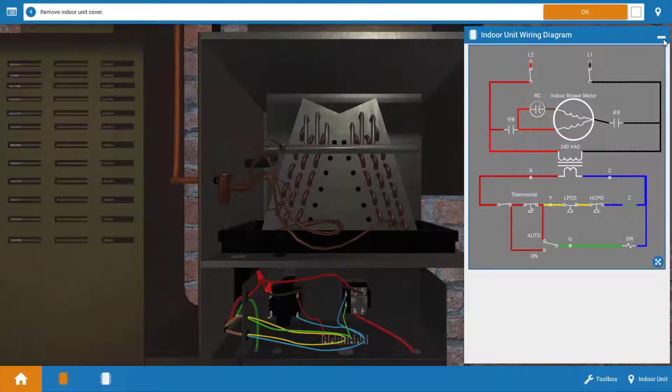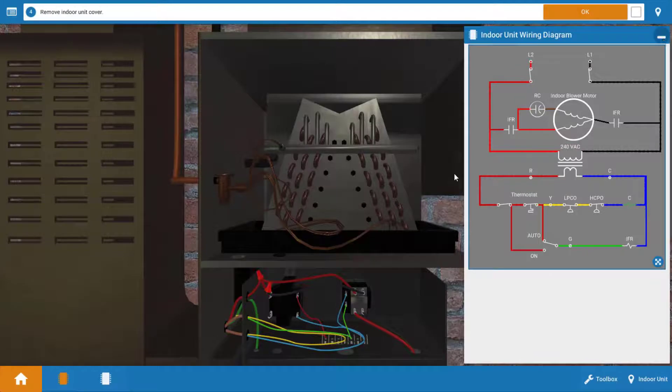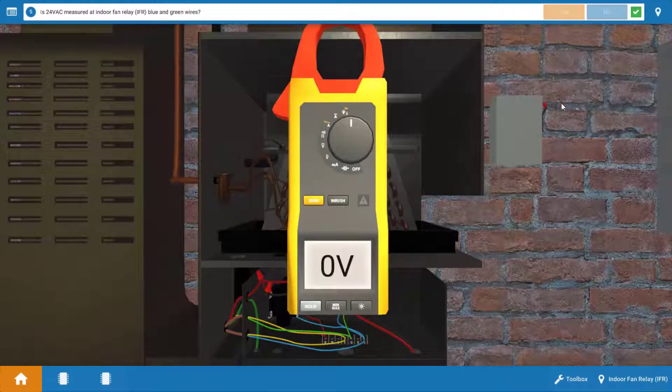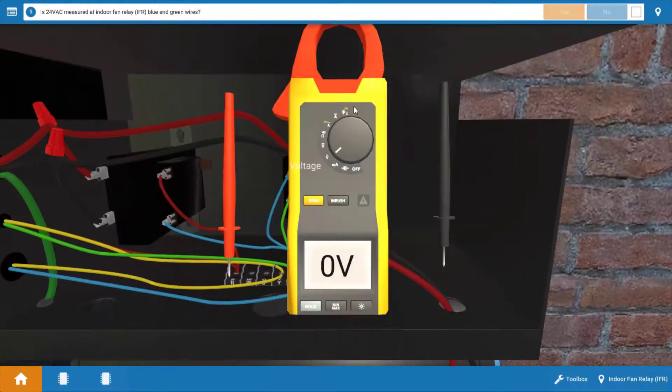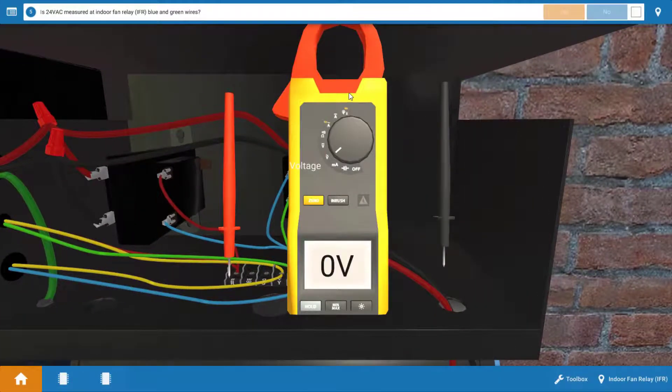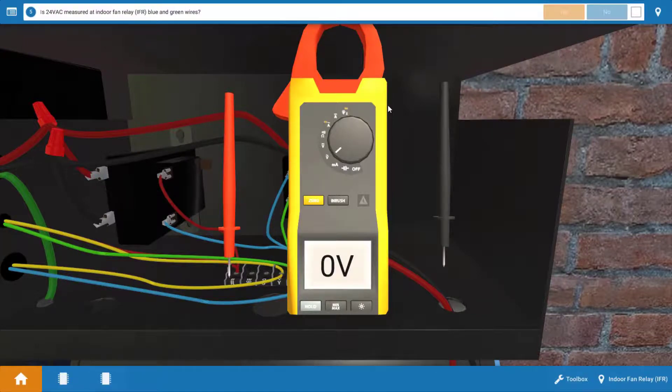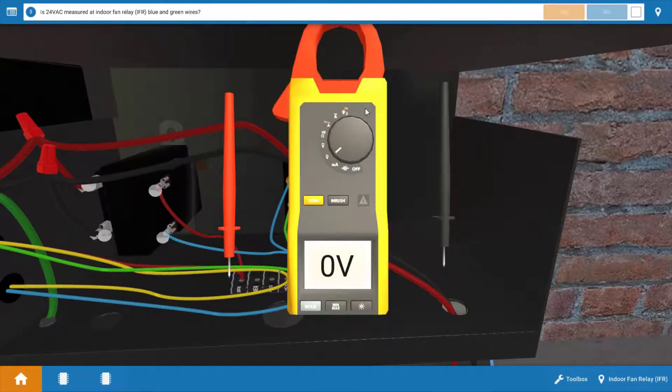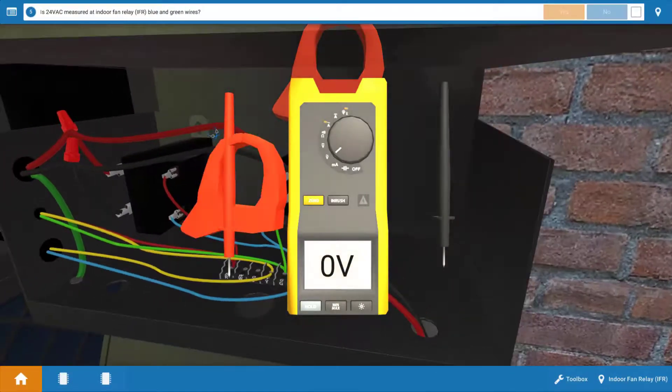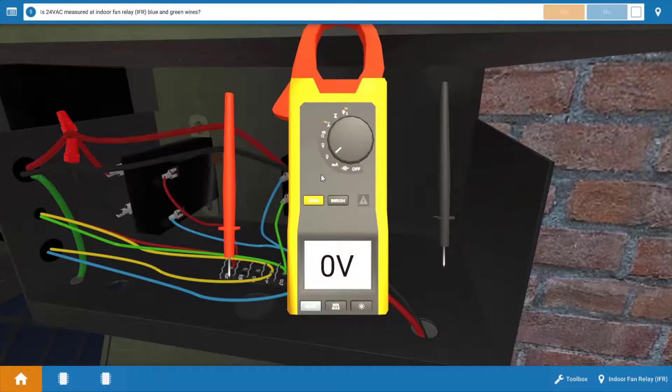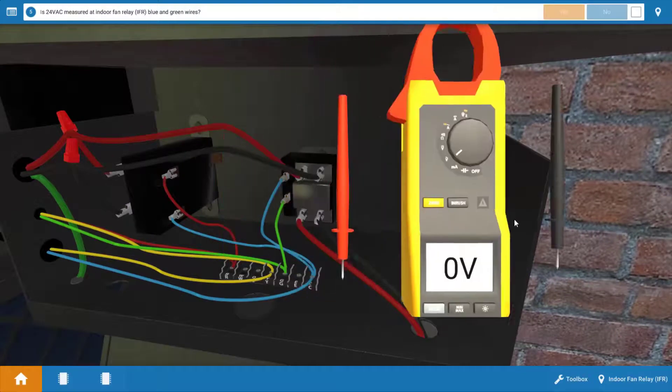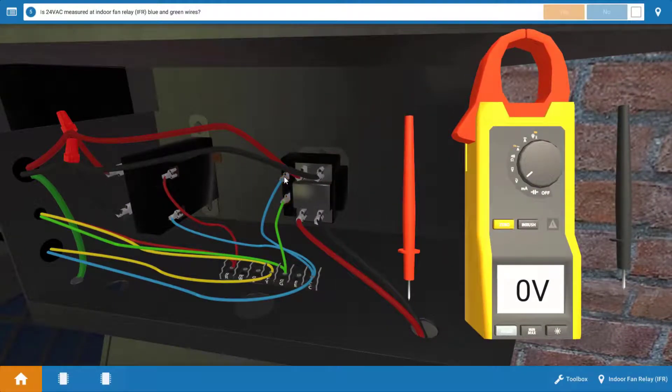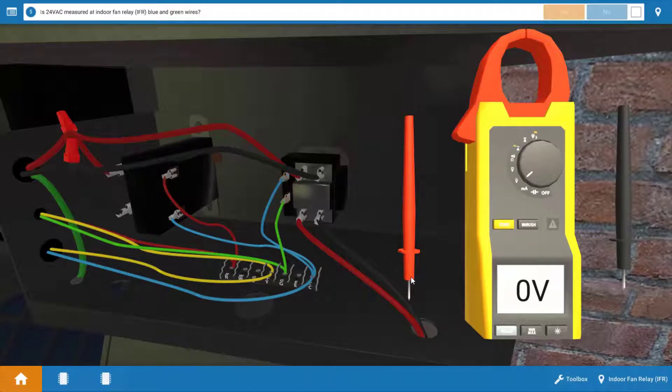Click OK on the procedure guide. And the first thing we're going to do is we're going to measure for 24 volts at the fan relay. Now we're going to do this at the coil of the fan relay. So just slide your meter out of the way and the coil is located between blue and green here and the two glowing orange hotspots.